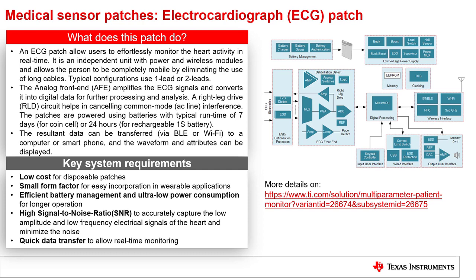The key system requirements for ECG sensor modules are: low cost for disposable patches; small form factor for easy incorporation in wearable applications; efficient battery management and ultra-low power consumption for longer operation; high signal-to-noise ratio, SNR, to accurately capture the low amplitude and low frequency electrical signals of the heart and minimize noise; and quick data transfer to allow real-time monitoring. A common block diagram for an ECG patch is also shown in the slide.